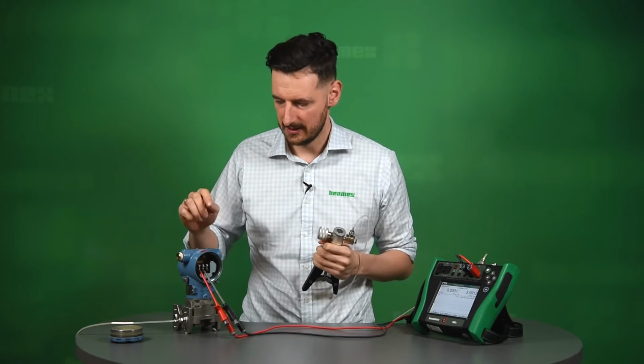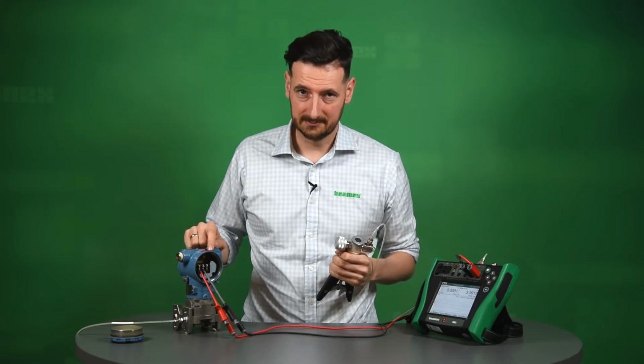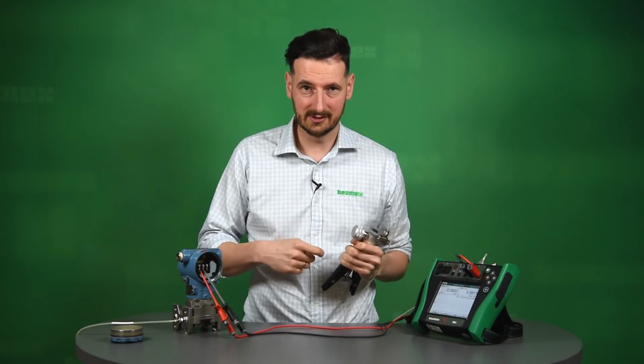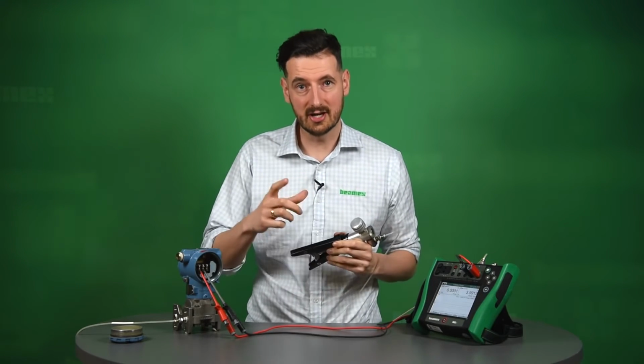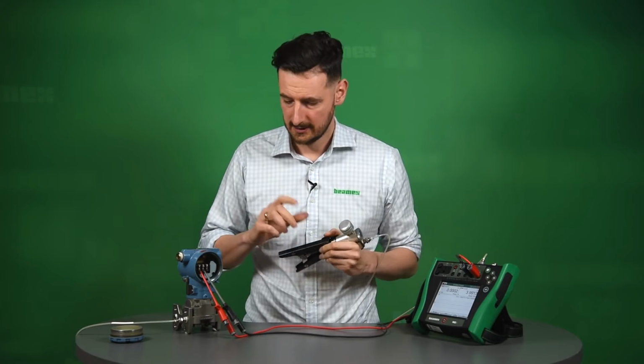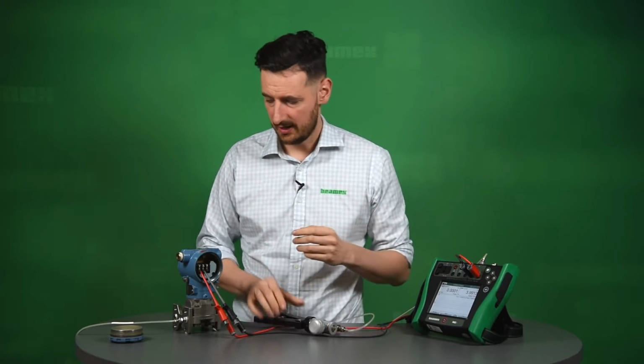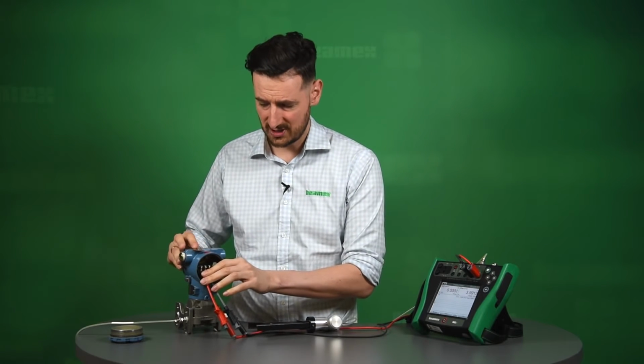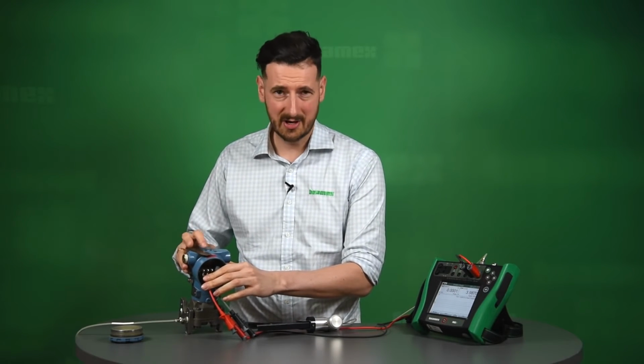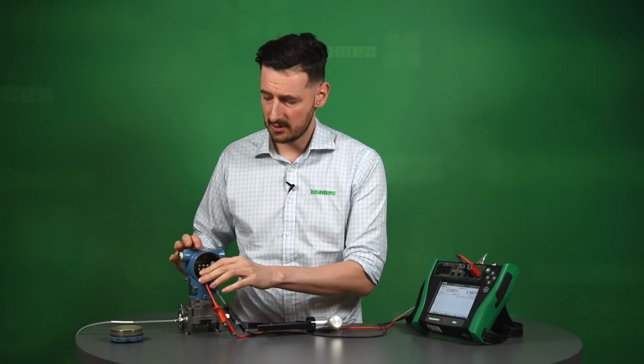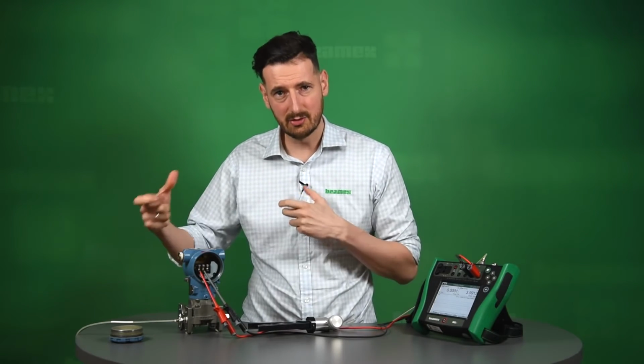There are potentially two ways we can do it. We know that's a Hart transmitter. We know we can use a Hart communicator to actually communicate with it and change those parameters that we want. But also some transmitters, not all of them, will have some sort of zero and span information here up top. Some companies allow you to press the buttons and do the span and the zero adjustment.